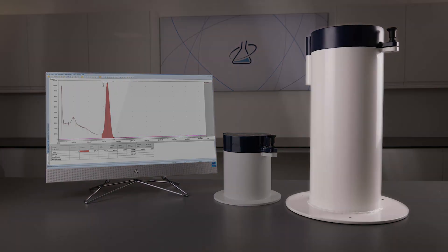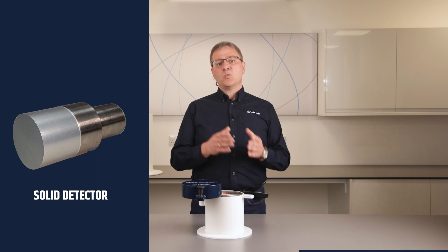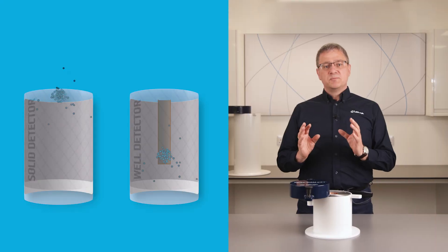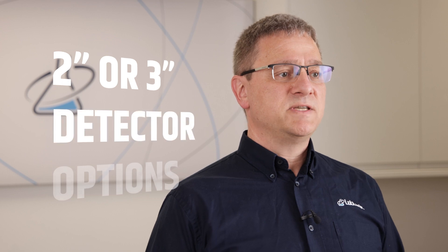First, the Spec-RAM is a gamma-spec system including a fully integrated scintillation detector and multichannel analyzer with 1024 or 2048 channels. It is available with either a solid sodium iodide or well geometry detector. Available in a range of sizes, the well-type geometries provide an almost complete solid angle coverage of the radioactive source. Both detectors are available in either 2- or 3-inch specifications.